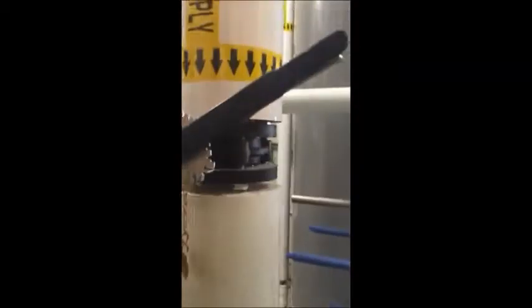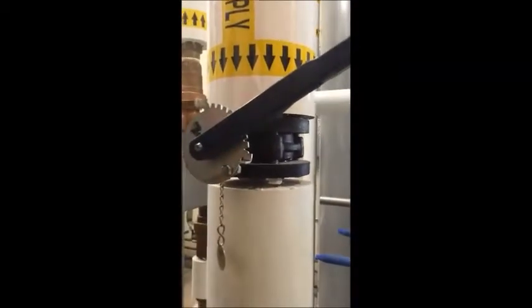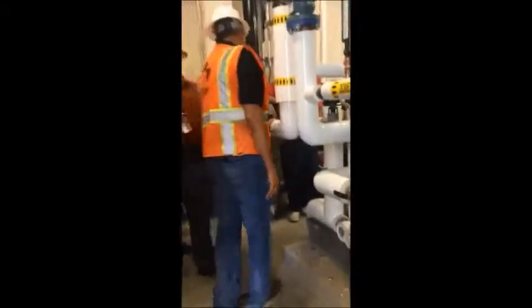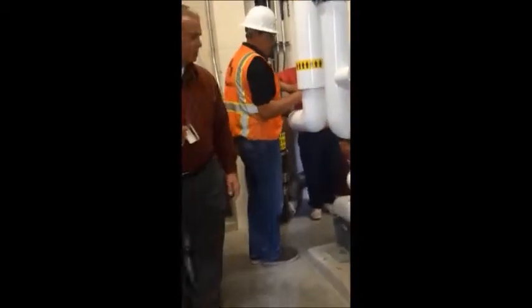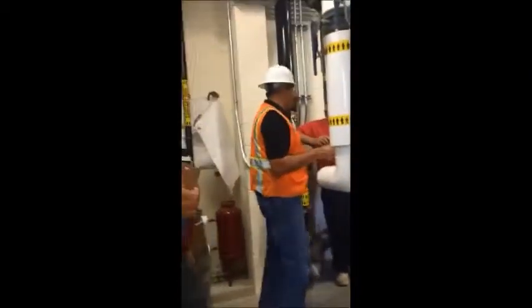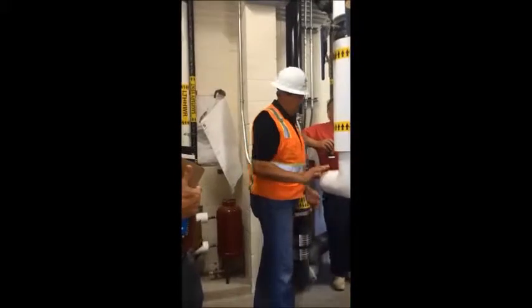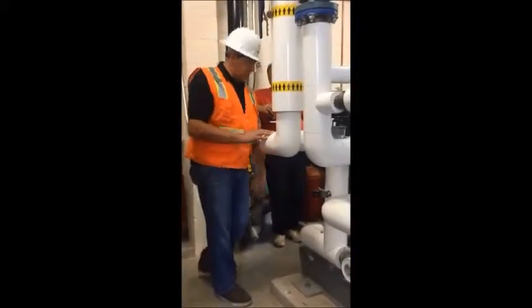we just added this, and it's an RFI. Do we have a marker for the butterfly here? That's the marker for the balancing of the exchanger. Yeah, and there is a Sharpie? Oh, yeah. Tim, thank you. So the real reason is technical: with this valve being open 100%, that's just feeding your 180 degree water right back to your plant. So I put an RFI in for this to see either changing this valve to a two-way or actually putting a valve in the bypass. The comment back was just put a valve in the bypass, but it was, I guess, never closed.